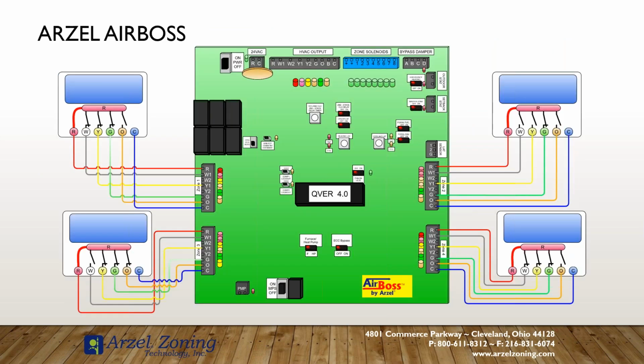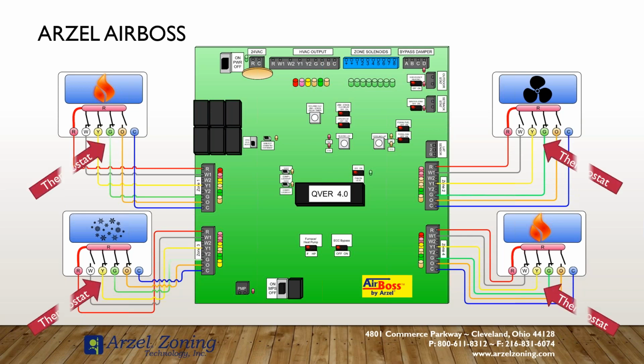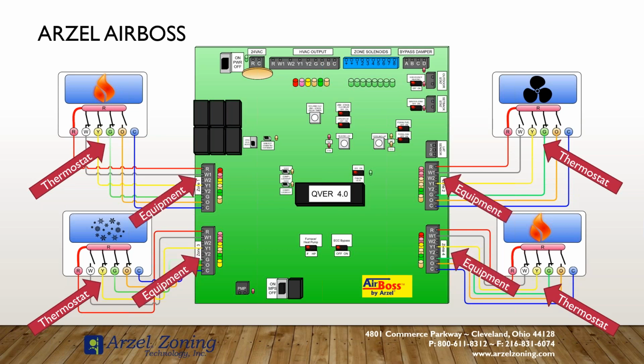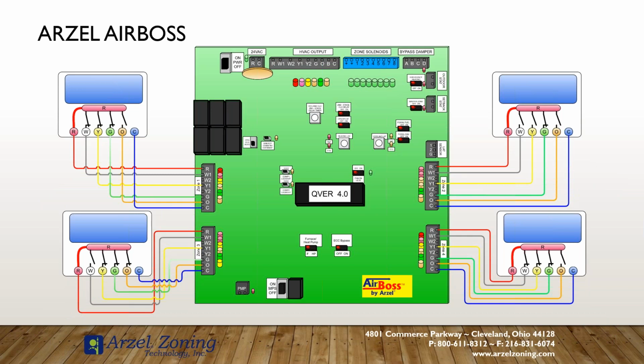The AirBoss is very similar to the Heat Pump Pro. We can have heating calls come in. We can have a cooling call come in. We can have our fan call. Our thermostats are just that. They're a thermostat. From the thermostats, we move to the panel. Each zone connection is our equipment in relationship to that individual thermostat. And then from there, our HVAC outputs are the thermostat in relationship to our equipment. So we start at step 1. We turn our thermostats on.